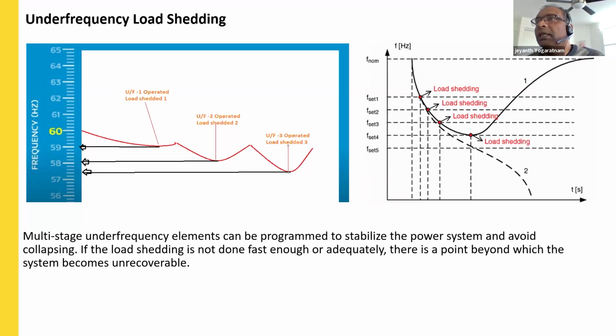The frequency is expected to stabilize at the normal frequency. However, if the load shedding is not at the correct speed, and the generation starts to reduce further while the load starts to increase, sometimes the load shedding may not bring the system back.